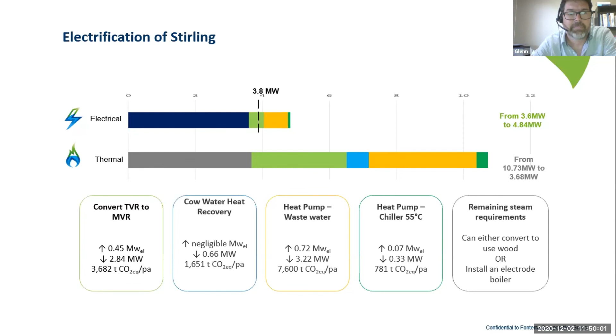Again, you can see that increase on the yellow bar there, and a really significant reduction in steam use. Ultimately, what we're left with is some residual steam demand for various processes that require a higher grade heat than what can be achieved with industrial heat pumps. We thought the thing to do there was to use a smaller package electrode boiler, which had some fantastic technical attributes, but is hellishly expensive to operate.